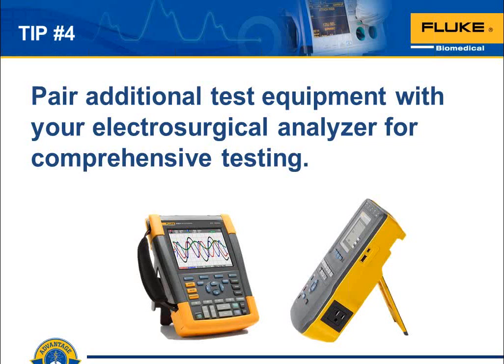Whether or not you're going to use the same ESU analyzer for cal adjustments as well as performance verification, you should be looking at those wave shapes, because the nuances in the wave shape will tell you a huge amount of information qualitatively about whether that ESU is likely to fail during clinical use if you put it back in use after your testing. Your numeric values could be perfect, but your wave shape could indicate that you've got some problem with power amplification or things like that. So take a look at that.